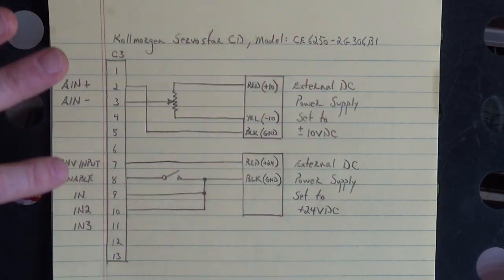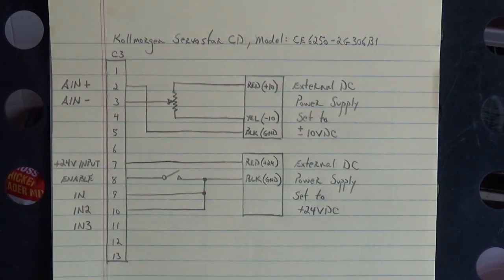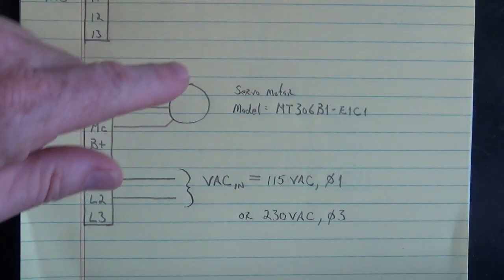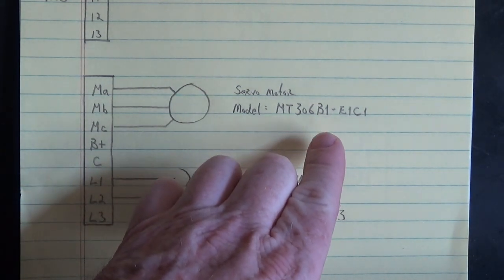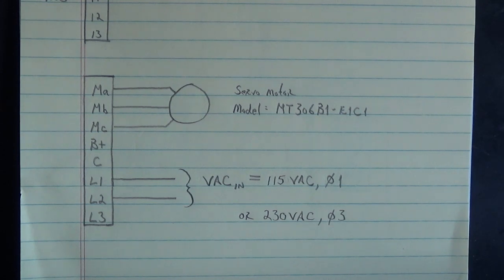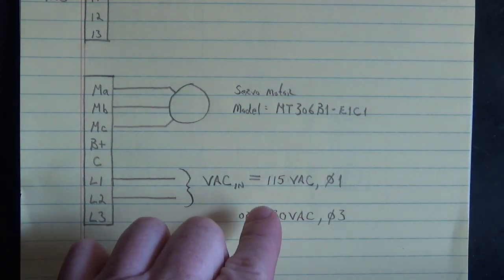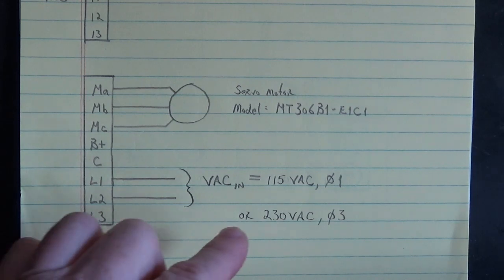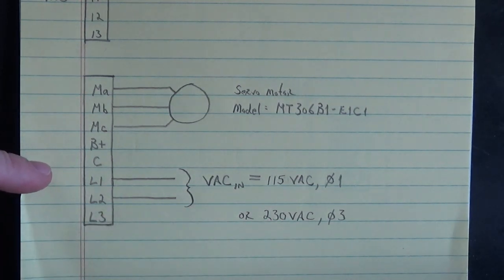That's all I need to run that servo motor. Now let's go down to the motor connections. The servo motor Kollmorgen model MT306B1-E1C1 connects to MA, MB, and MC. For line voltage you have a choice — which is really nice — between 115 volts AC single phase going to L1 and L2, or 230 volts AC three phase going to L1, L2, and L3.